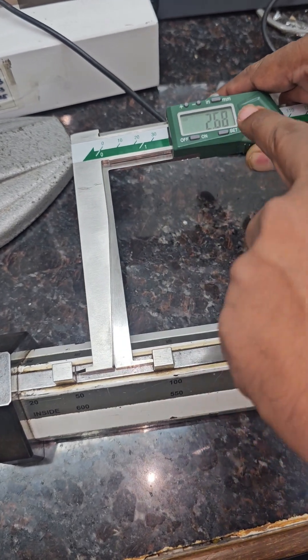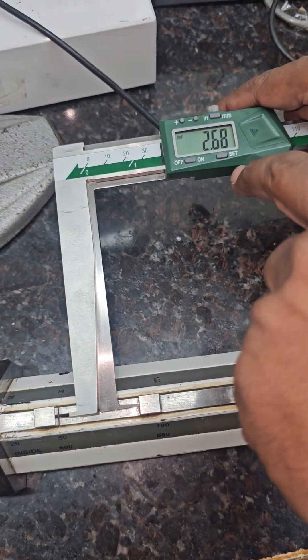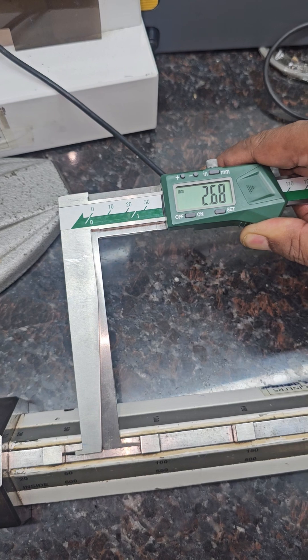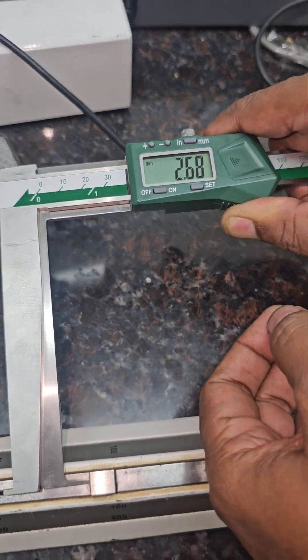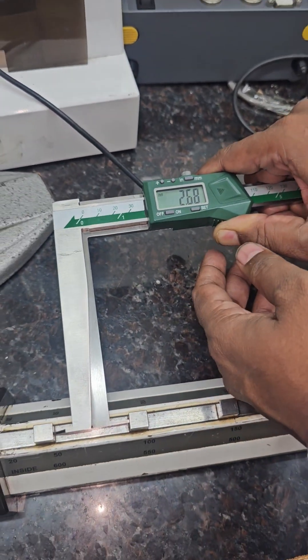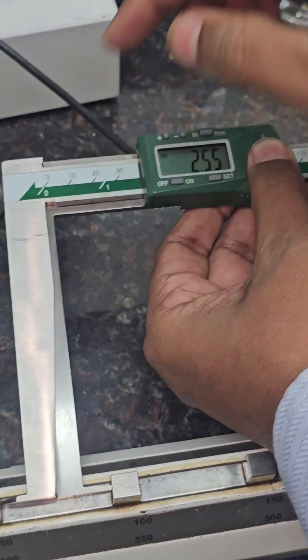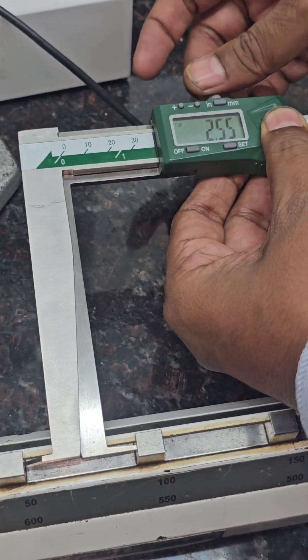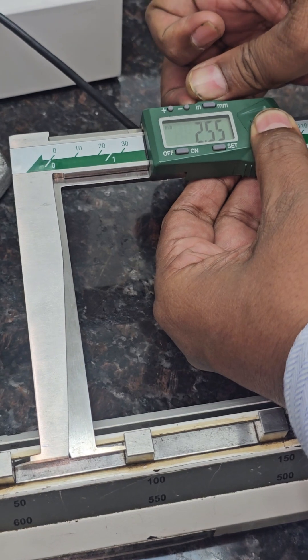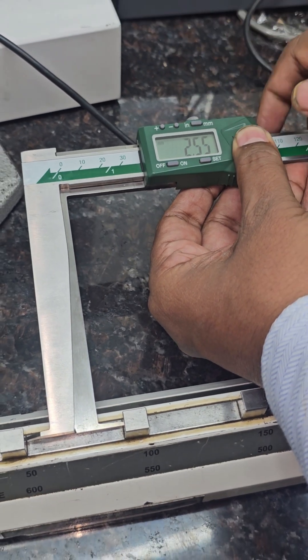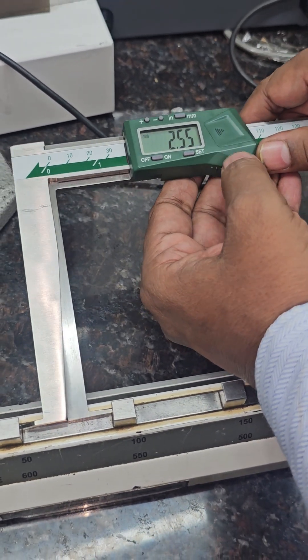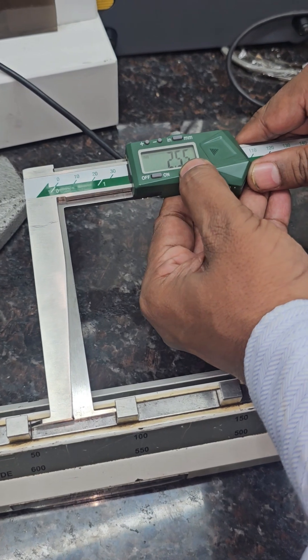It's showing 2.68. Now we can set this. The actual distance is 40mm, that's why first we lock the inside groove caliper, then press set button.